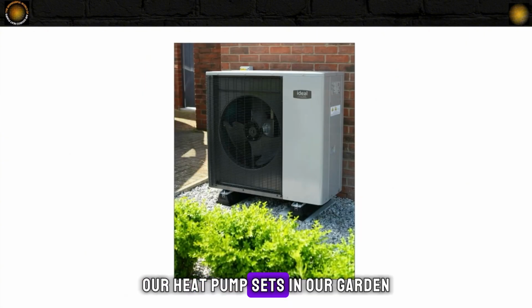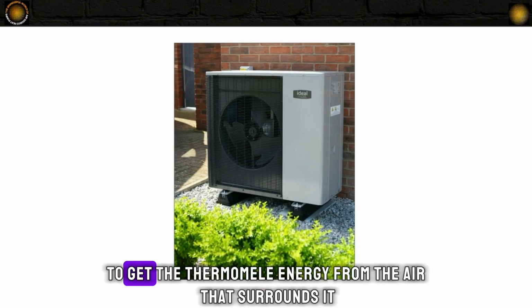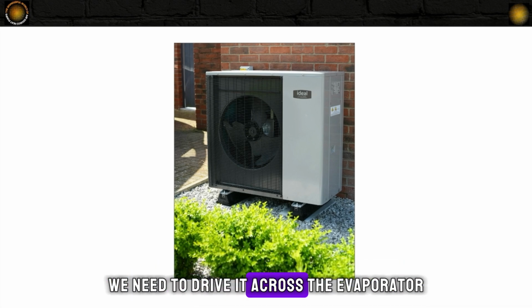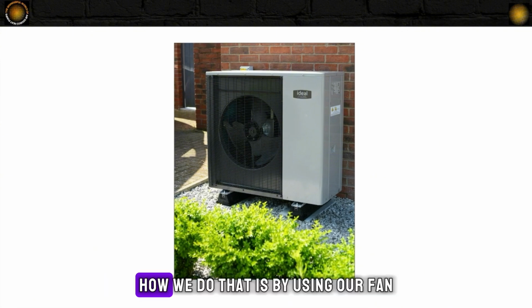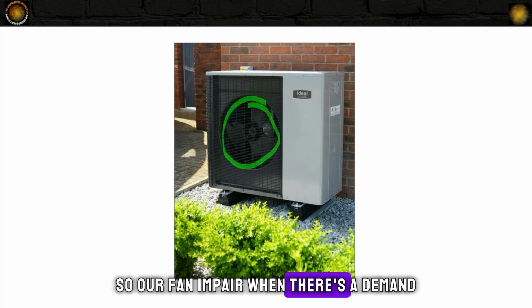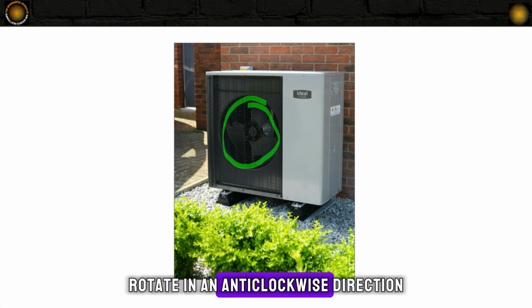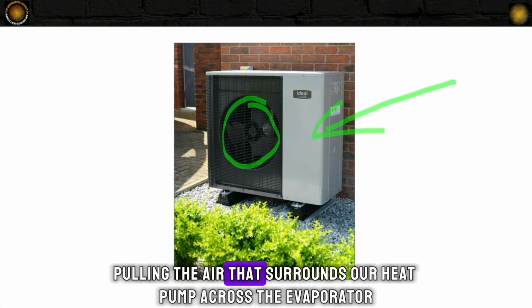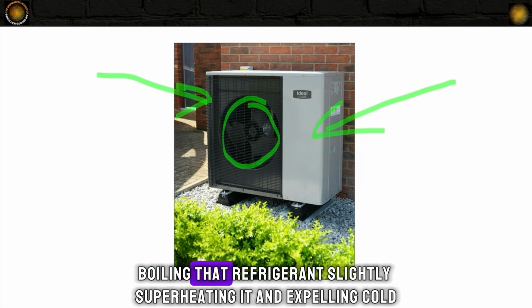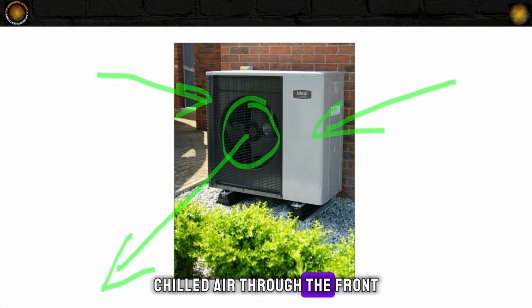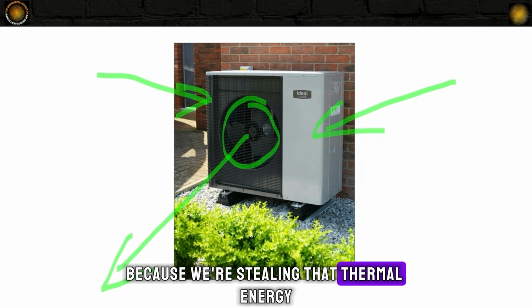Now, our heat pump sits in our garden. To get the thermal energy from the air that surrounds it, we need to drive it across the evaporator. How we do that is by using our fan. So our fan impeller, when there's a demand, will rotate in an anti-clockwise direction, pulling the air that surrounds our heat pump across the evaporator, boiling that refrigerant, slightly superheating it, and expelling cold, chilled air through the front because we're stealing that thermal energy.